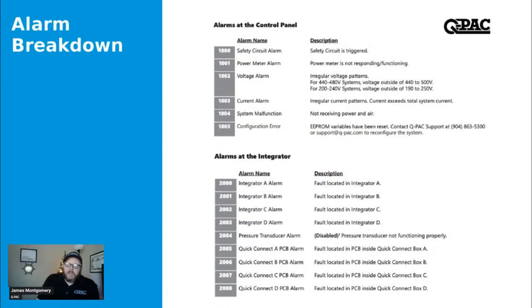There's only a couple of things that could cause this safety circuit alarm to go off. The first one being that you didn't make the connection between 24V and DI1 that I talked about. That's where we expect to see your dry contact or a jumper. If that's not there, safety circuit's going to always be active. Unit won't run. It's directly in series with the coil on our M1 contactor. For those who don't know, the M1 contactor is a contactor that we've installed, and it's how we take the voltage that comes in, we send it downstream or out the contactor to the quick connect box. So without energizing that coil, you won't pull that contactor in, you won't have power to the fan section.